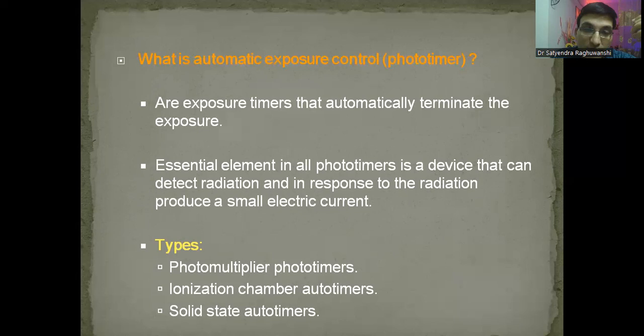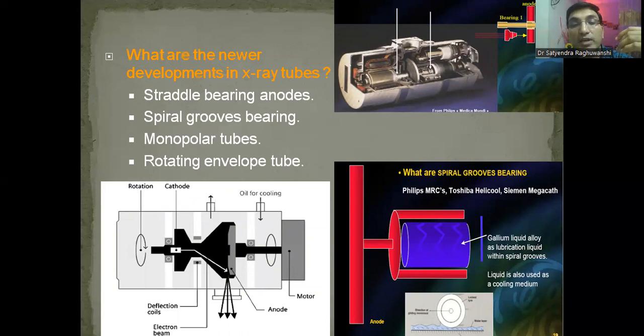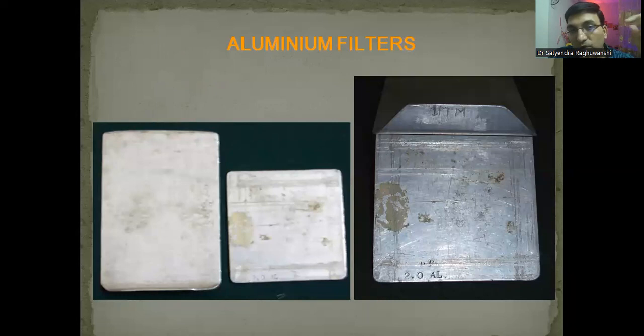What is automatic exposure control or phototiming? In latest x-ray machines and digital mammography machines, we have AEC — automatic exposure control. What happens there? We have a phototimer, and when an x-ray beam passes through it, the machine automatically decides how much exposure is to be given and what the duration of exposure should be. This is more than enough for table viva. What are the newer types of x-ray tubes? Simply remember the names: straddled bearing anodes, spiral groove bearing, monopolar tubes, and most importantly, rotating envelope tube — where the whole envelope actually rotates.